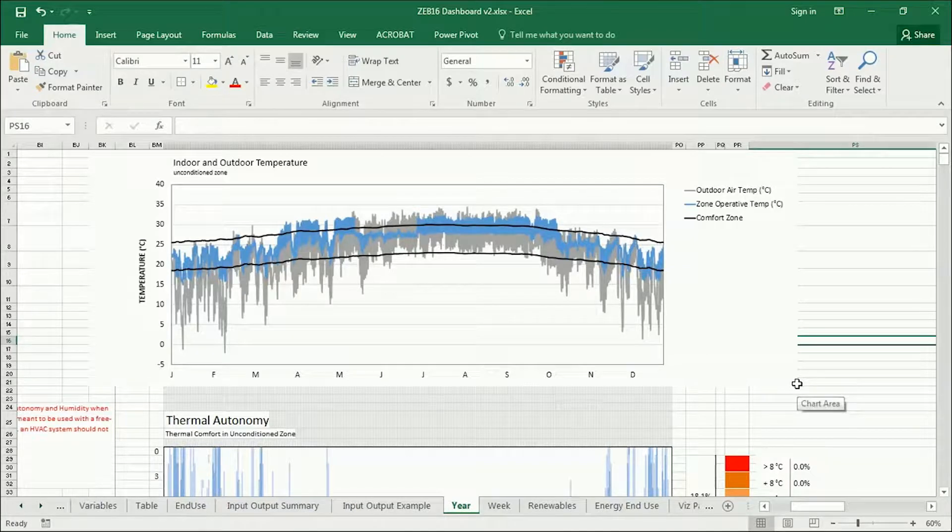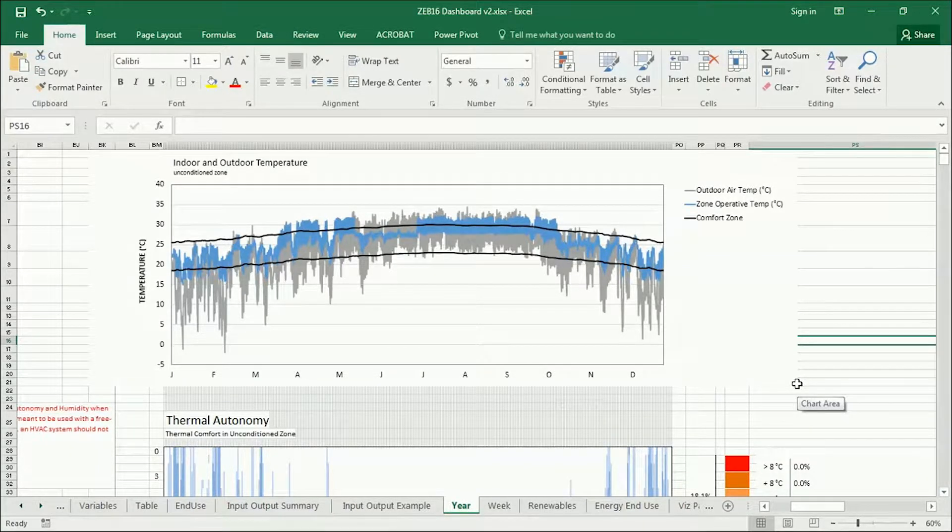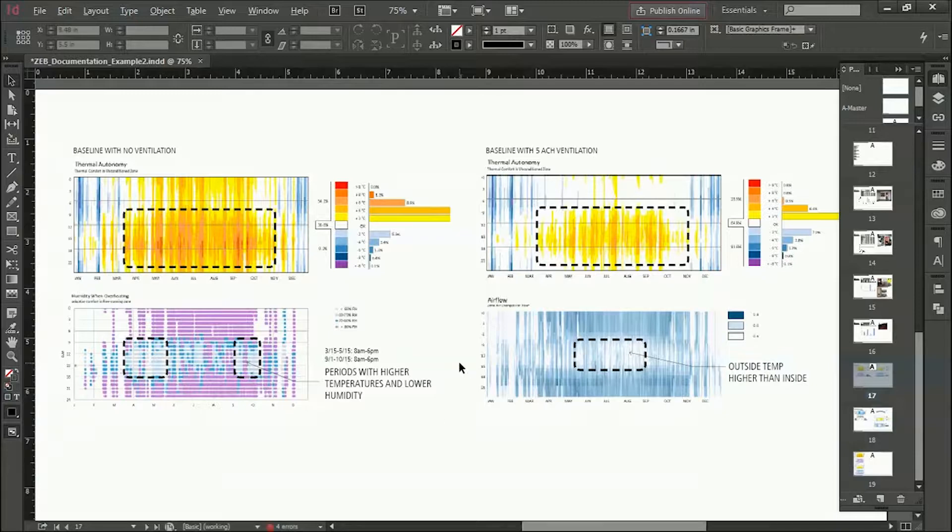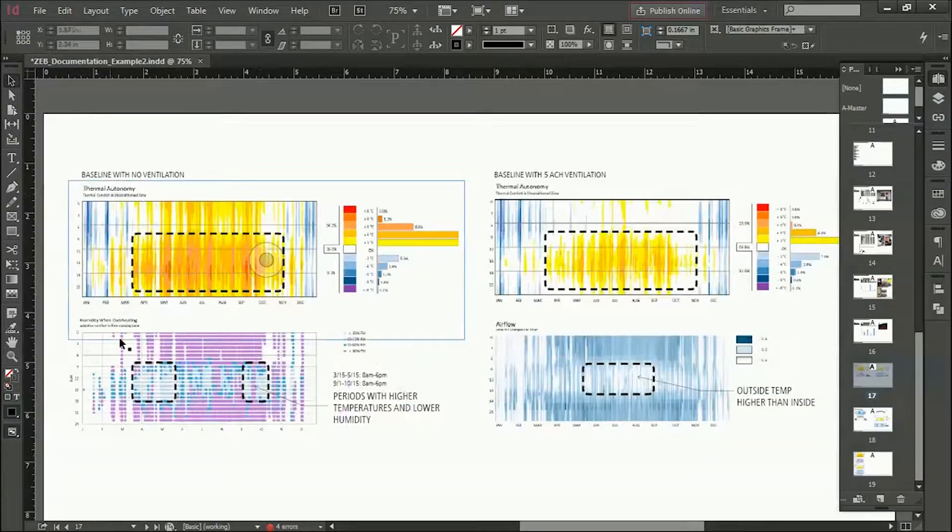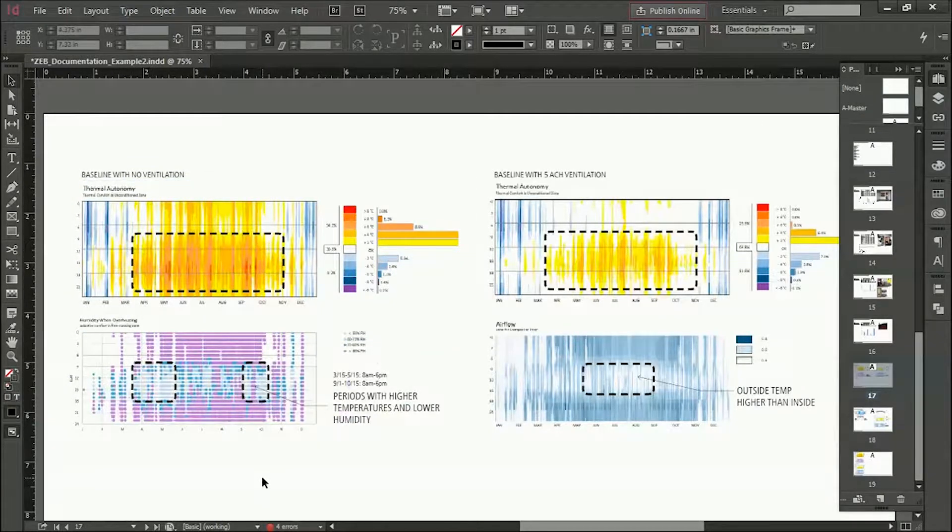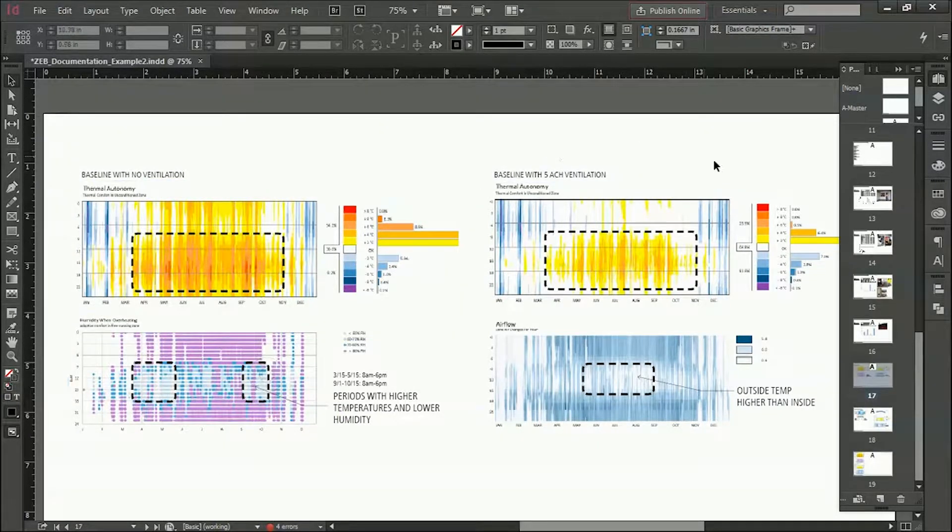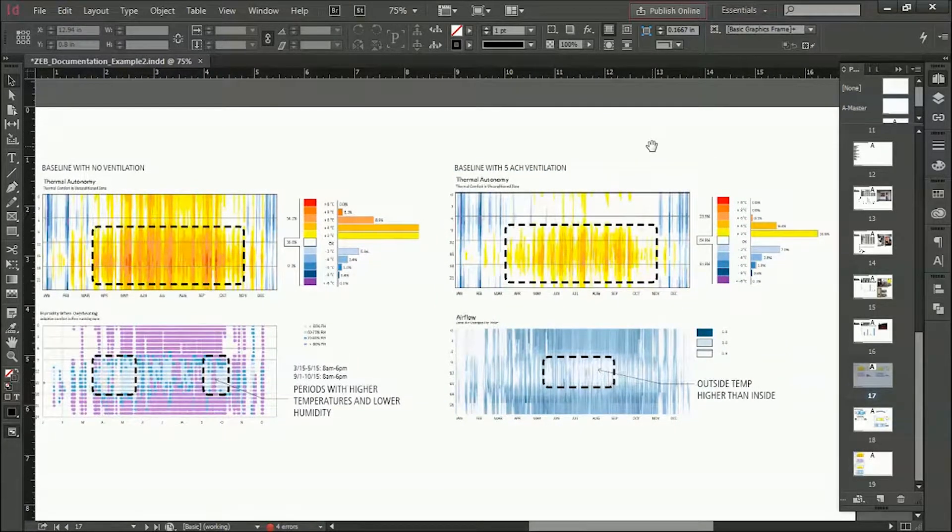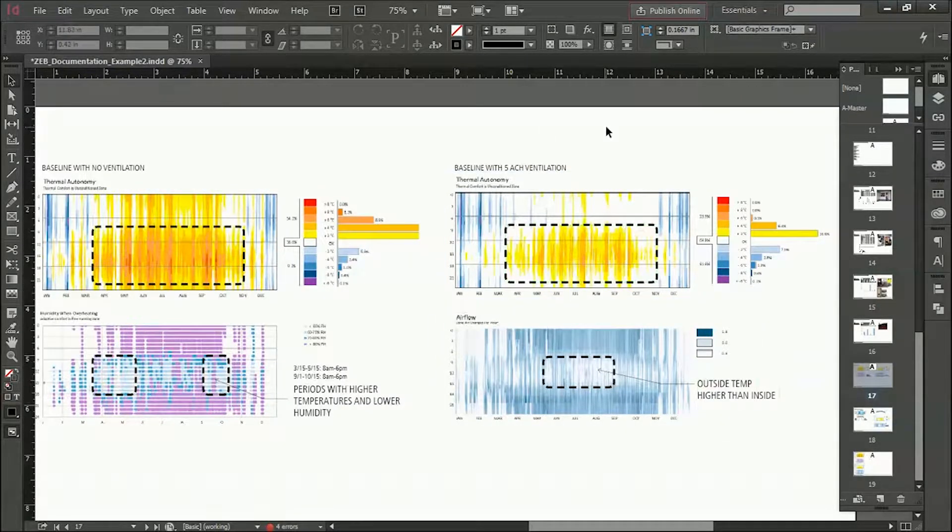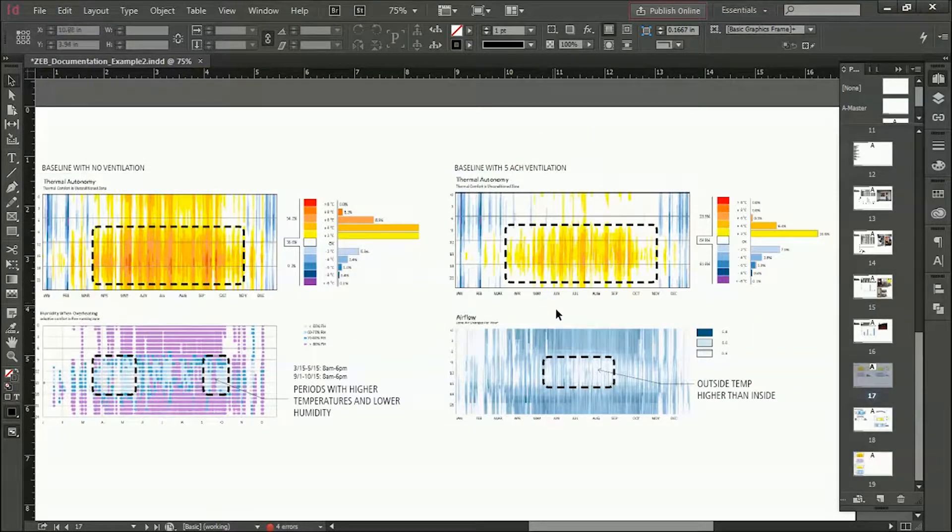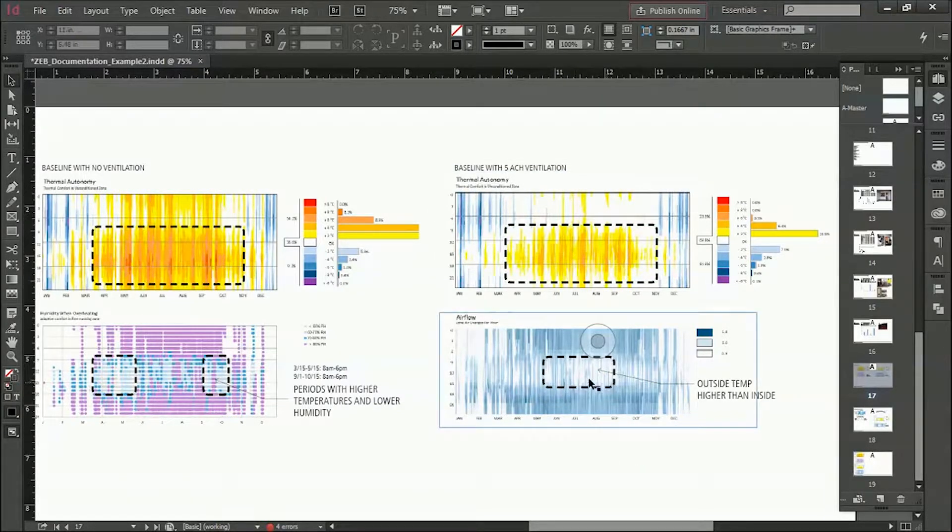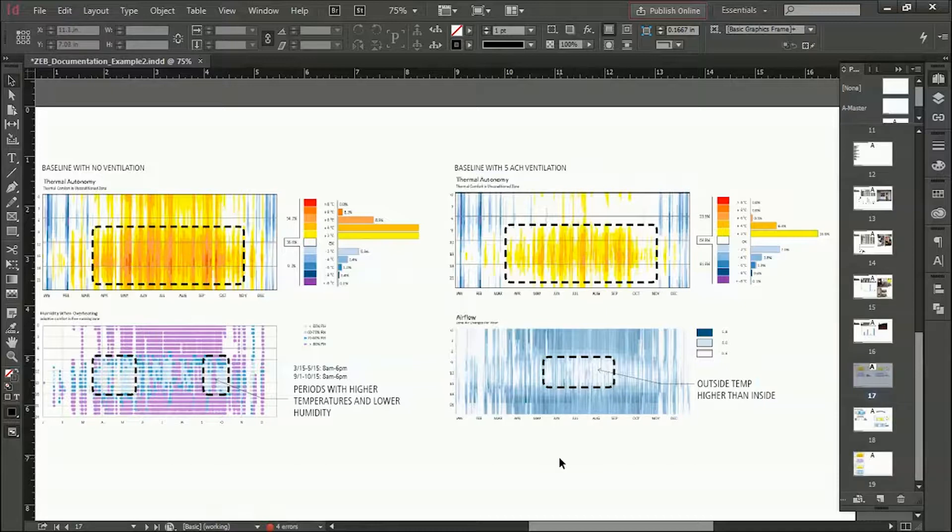I'm going to output these and save them or export them as PNGs and then lay them out in InDesign. So here we have the first set of runs on the left. The baseline with no ventilation where we had an extremely overheated zone and we were able to see where the periods of higher temperature and lower humidity existed. Then we ran with five air change per hour ventilation rates for a constant fan, and we were able to see then what the possibility for natural ventilation might be. We also could see that there were times when even with more ventilation, the outside temperature is higher than the inside, so there wasn't really the possibility of using that. If you wanted it to be cool, you'd need to use air conditioning.